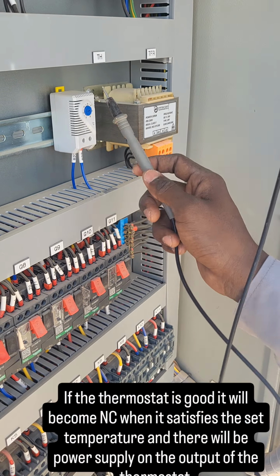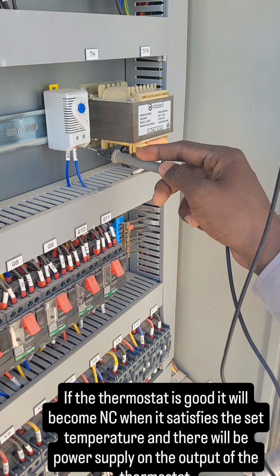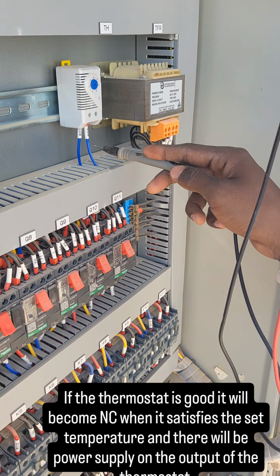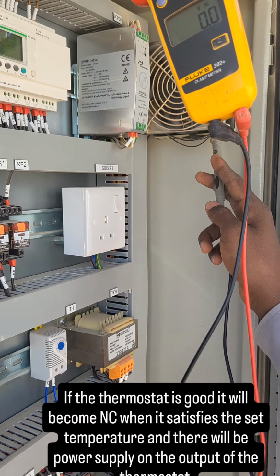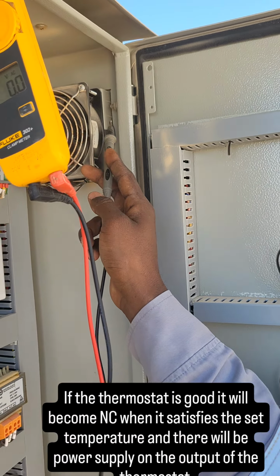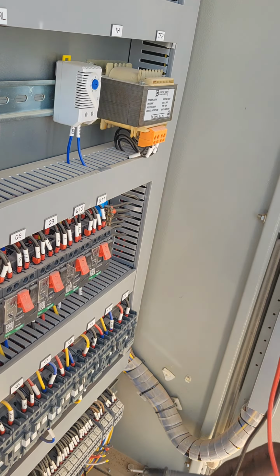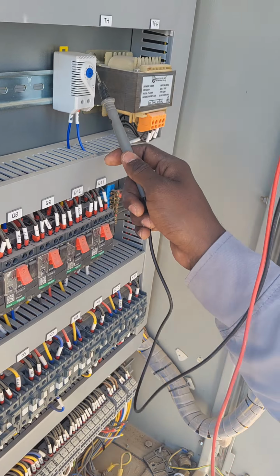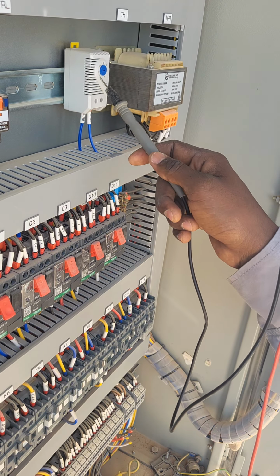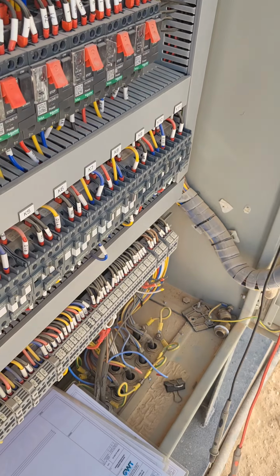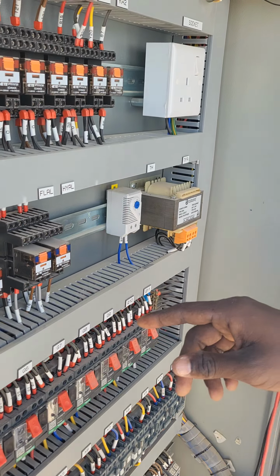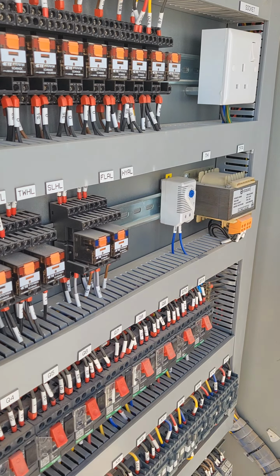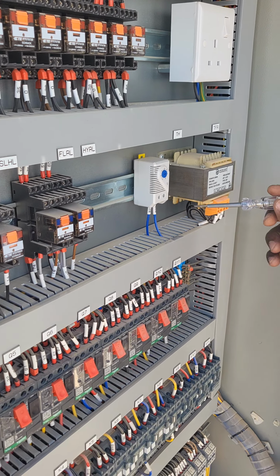For this, the thermostat should match the condition or the set value, and only then will the thermostat become NC, get phase voltage, and the fan will run. The set temperature on the thermostat is 26, but winter is going on now, so the temperature is still 22. So it will become NC when the temperature matches the thermostat's set temperature.